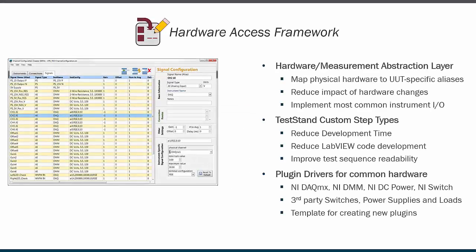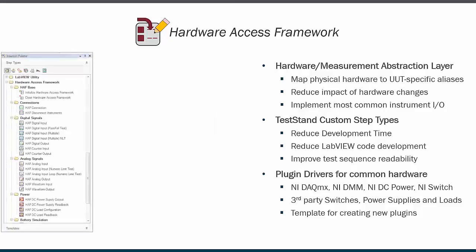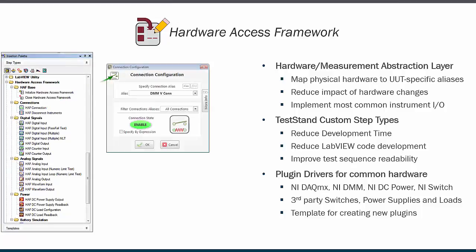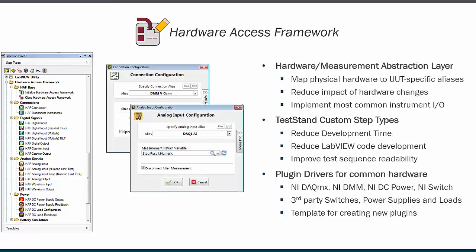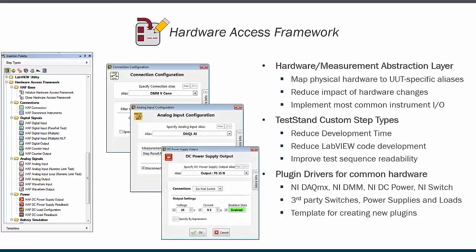The hardware access framework is a hardware and measurement abstraction layer for NI Test Stand. The HAF links hardware configuration information to human-readable signal aliases using a channel configuration file. It then provides Test Stand step types or actions — like make connection, read analog input, or configure power supply — that directly link to the configuration file to allow sequences to be developed from the point of view of the unit under test rather than the instrumentation.